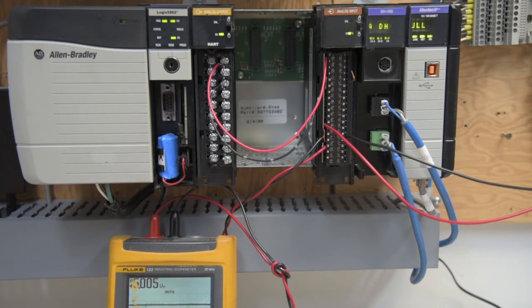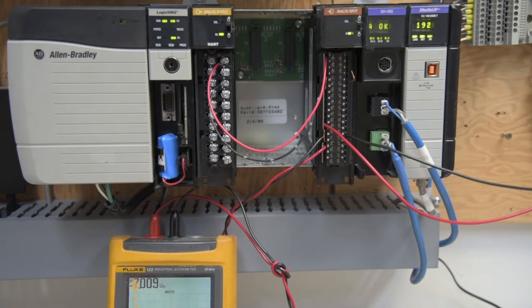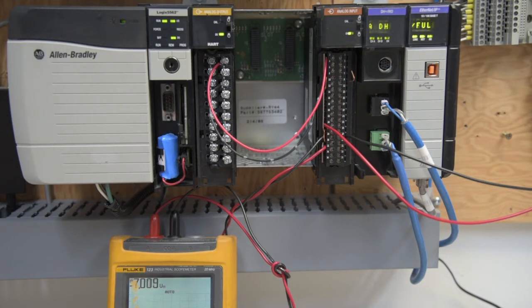And we'll just do a negative voltage, minus 7, and we're at minus 7.0089. So, it shows that our output module is quite accurate.